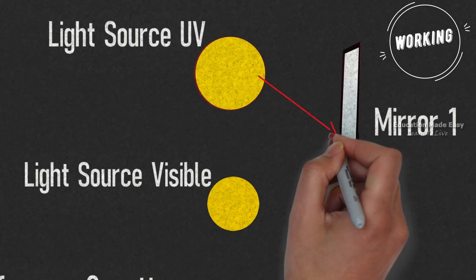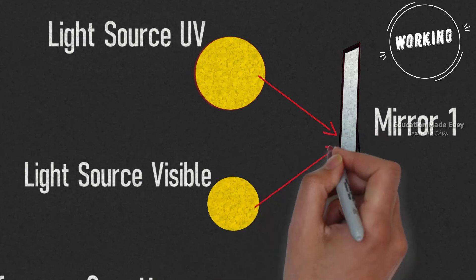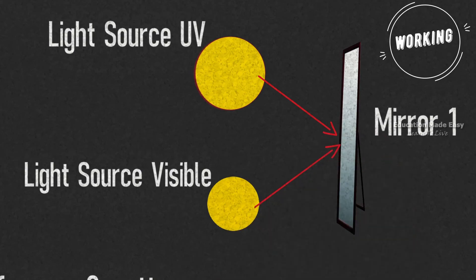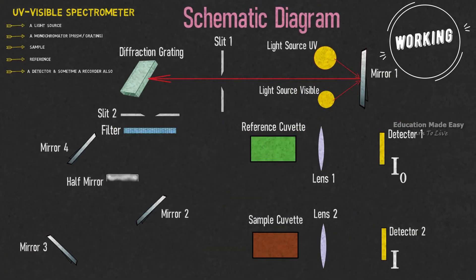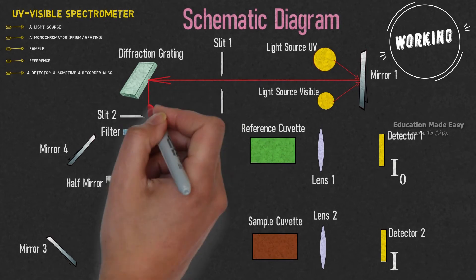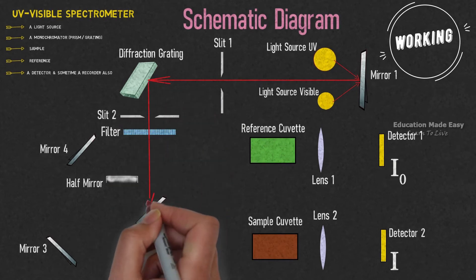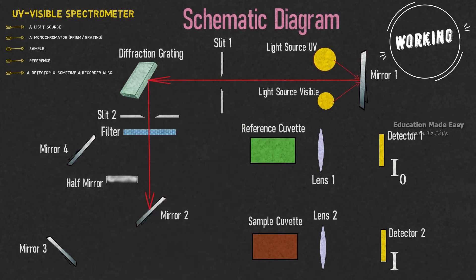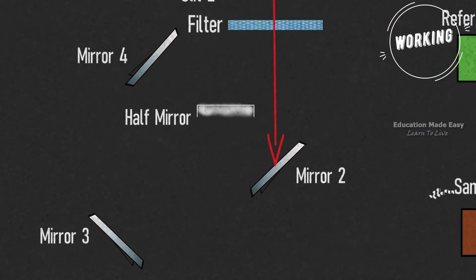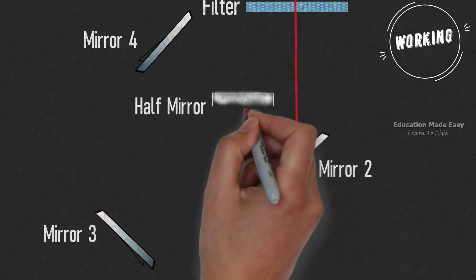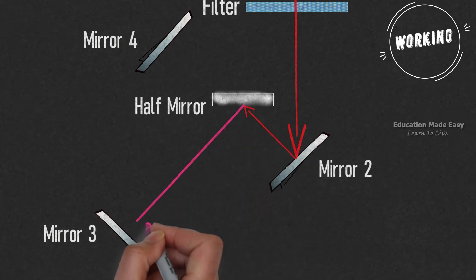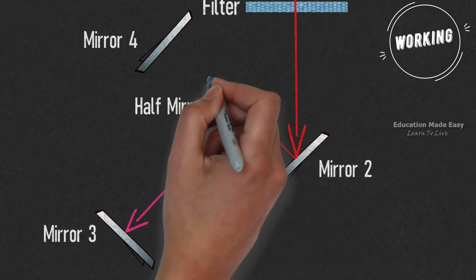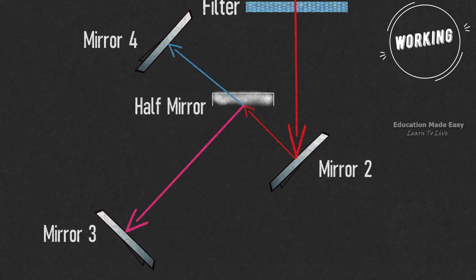The light beams from light source UV and light source visible hit mirror 1. Mirror 1 reflects the light beam and passes it to the diffraction grating through slit 1. The diffraction grating reflects the light to mirror 2 through slit 2 and the filter. At mirror 2 the light is again reflected to the half mirror. At the half mirror, a part of the light is reflected to mirror 3 and the remaining is refracted to mirror 4.